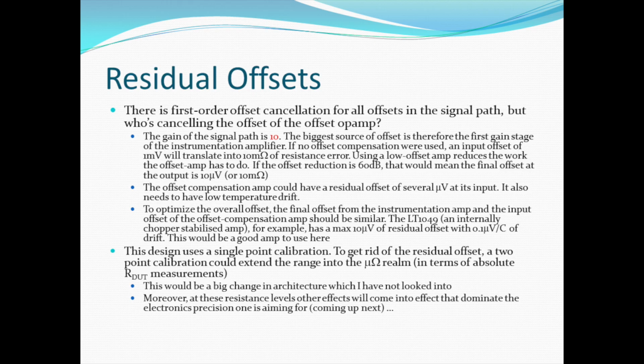A 2-point calibration, I think, would drastically change the design, and I haven't looked into that in this particular setup. I haven't even studied it. It's possible, I bet, but most of the simpler designs that you see on the internet are 2-point calibration, where I think they set the slope at the 2 points, which helps to improve the accuracy within that range. I think once you go to the sub-milliohm region, other effects like mechanical effects and positioning play much more of a role than just the electronic effects that I'm seeing over here. So I think we'll have to look at that next in terms of overall accuracy.